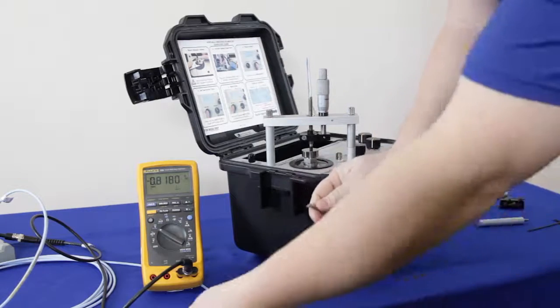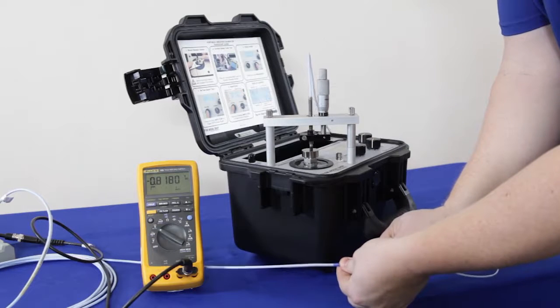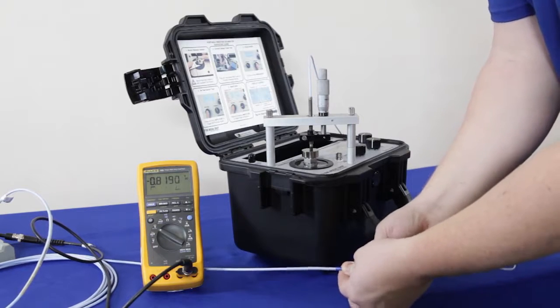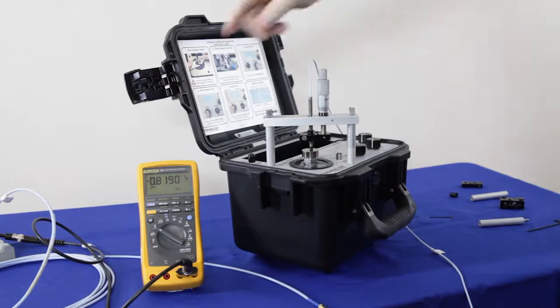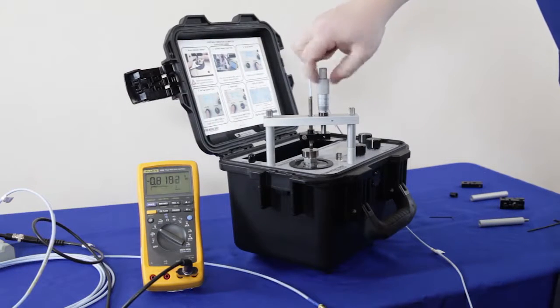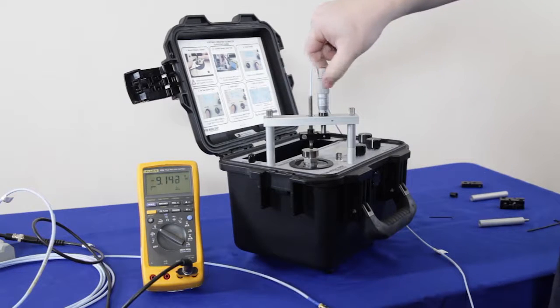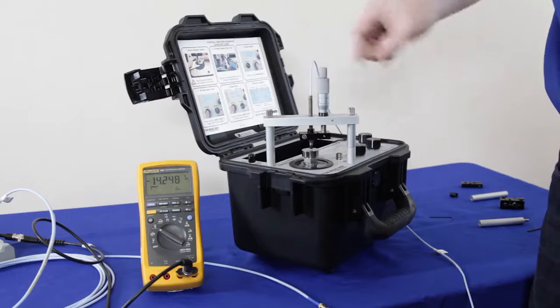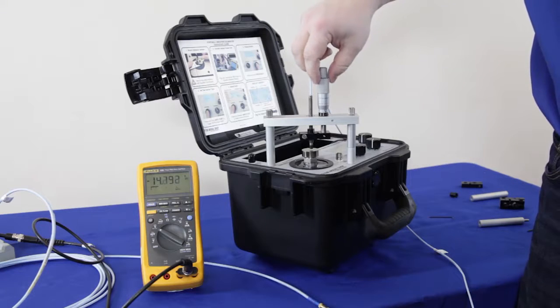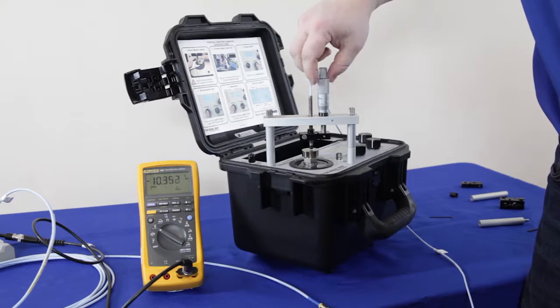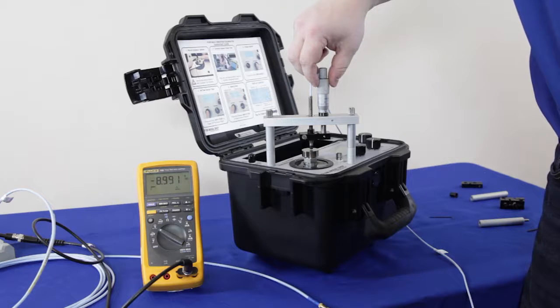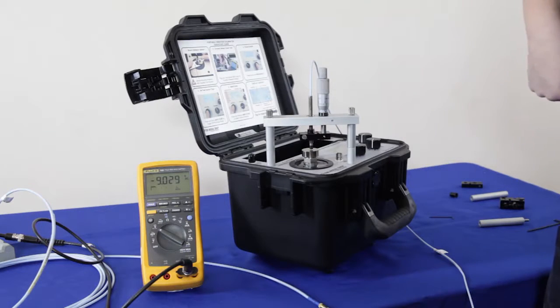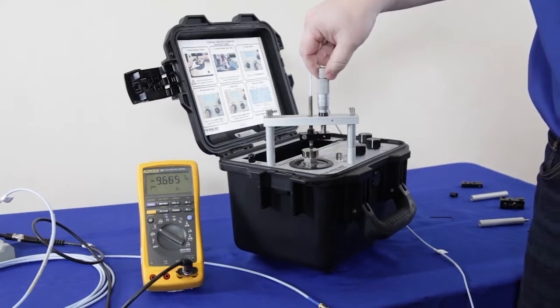If I connect the end of the probe cable to the extension cable, you will see an output on my Fluke voltmeter here. I have to move a little bit further away from the target, and now I want to set my initial gap voltage at anywhere between -9, -10 volts. -9 means I'm 50 mils away from the target before I start to vibrate that target, which means that the target can move 40 mils in either direction and I can still measure it. -10 volts is another good gap voltage.